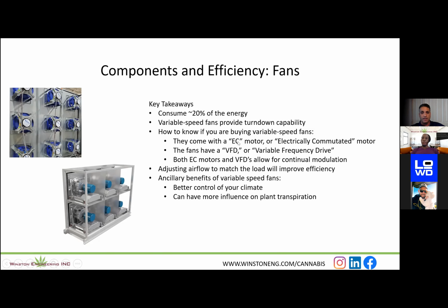So EC motors or EC fans, and then AC fans, or just looking for a VFD, what's called a variable frequency drive. Effectively, that's a piece of equipment that will cut the electrical signal to the fan itself to vary the speed of the fan, and you can adjust that by adjusting the hertz of the signal. So both EC motors and VFDs allow for continual modulation. They both are very good options, and really the only reason you'd use one over the other is some different constraints, whether it's space or whatever it may be, but you can effectively achieve the same result with both. So again, adjusting airflow to match the load will improve your efficiency. And then just like with the compressors, the ancillary benefits really are better control of your climate. And in this case with airflow, because airflow has such an impact on plant transpiration and obviously the things downstream of transpiration, you can have more influence on the plant transpiration if that's something that you desire.